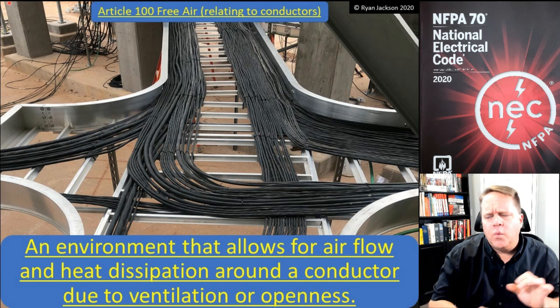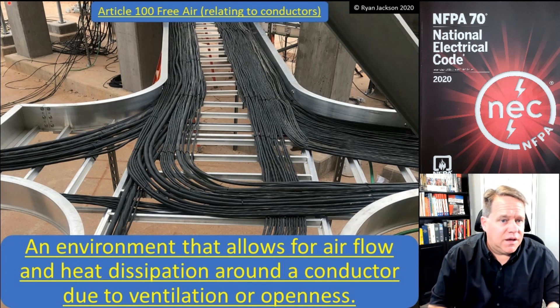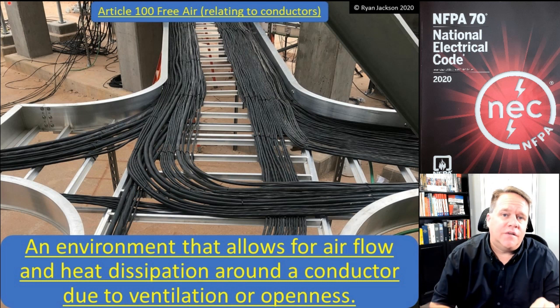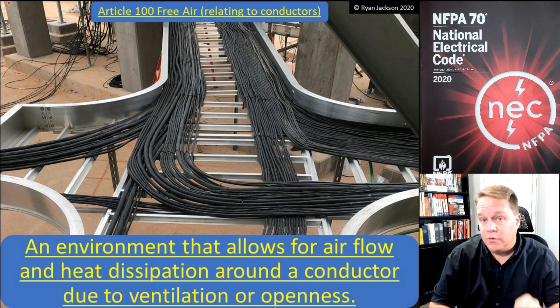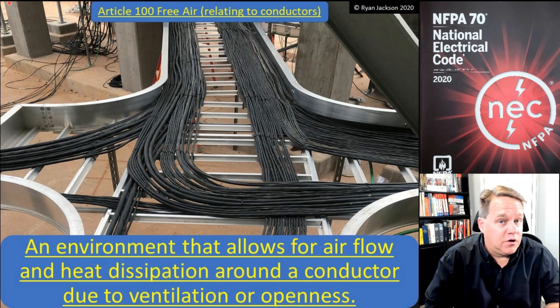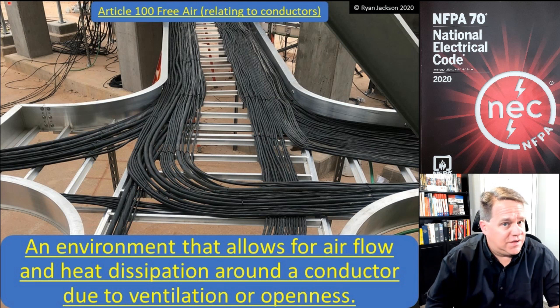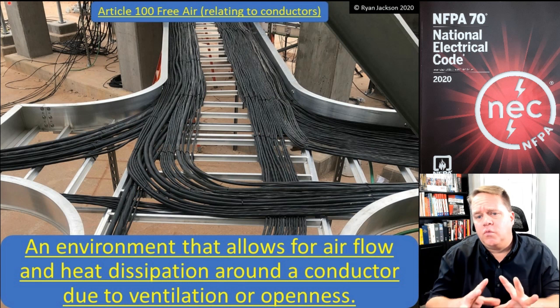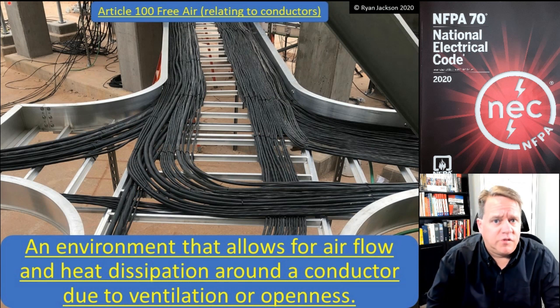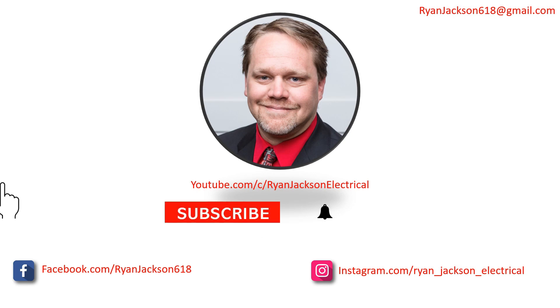When you go to Section 392.80, it talks about how to determine the ampacity for conductors in a cable tray, and sometimes we're allowed to use the free air table 310.17 instead of 310.16. So that's where the definition really becomes useful — when we start talking about cable trays.